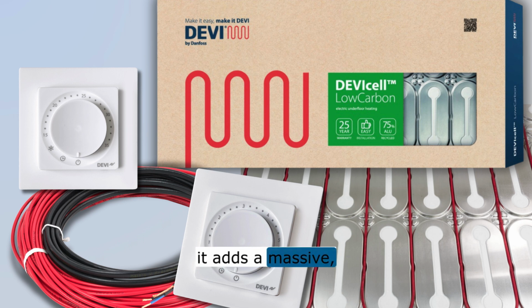But it adds a massive, bolded warning. The cable must be completely unrolled before you do this. Yes, this is a classic rookie mistake. If you power up a heating cable while it is still tightly coiled on its shipping spool, the heat has nowhere to dissipate. So it just bakes itself. Exactly. The center of the spool acts like an oven, and the cable will melt its own insulation into a solid, useless block of plastic in minutes.